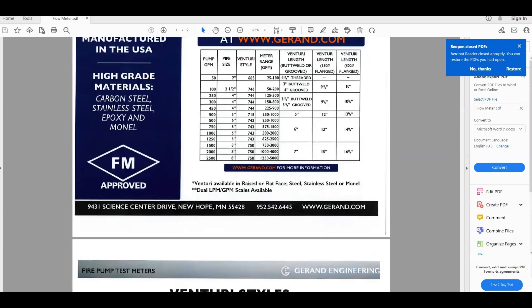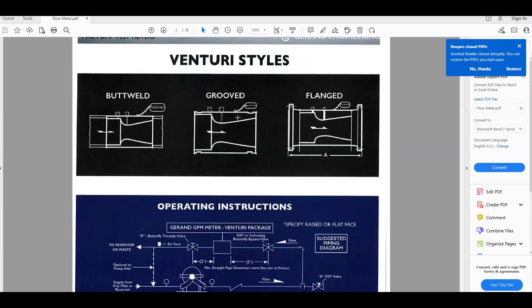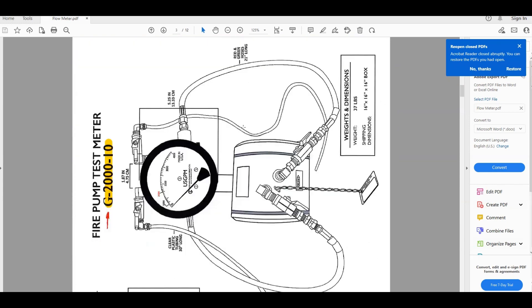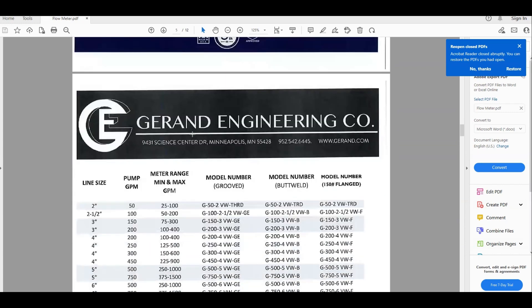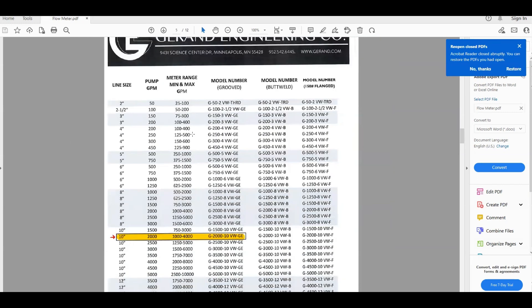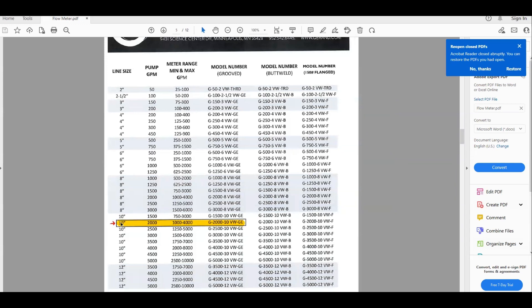We have the catalog here. This one is the Grooved one, so I'm going to use this one. This is now the model. This is the table on how to select the sizing based on the pump GPM capacity, and it also depends on the minimum and maximum meter range. As you can see in the table, for a pump GPM of 2000, this is the valve size we're going to select and this is the model.